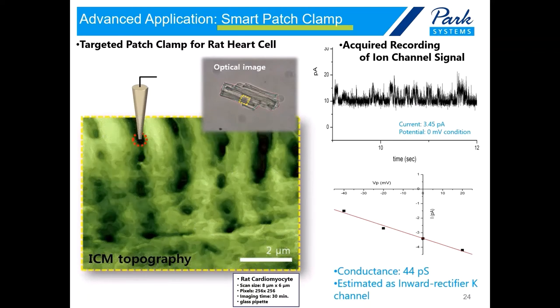In advanced applications, we can use SICM as a tool for smart patch clamp. In general, patch clamp experiments are conducted blindly without knowing the surface where the pipette lands. However, with SICM we can see the target area before attempting patch clamp, which gives tremendous advantages to researchers. Instead of using a micropipette with a 1-2 micrometer opening diameter typical for general patch clamp, we can use a nanopipette with an opening diameter of approximately 100 nanometers, giving higher resolution for ion channel mapping.